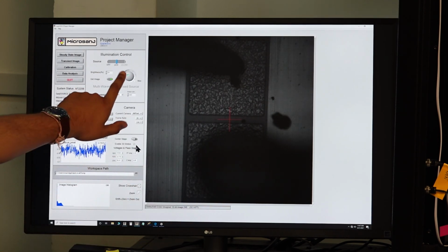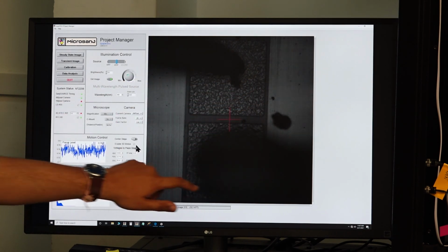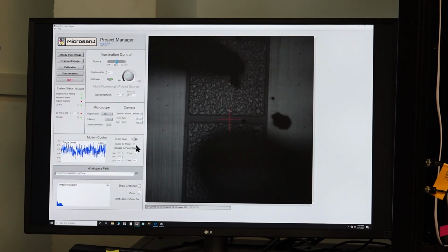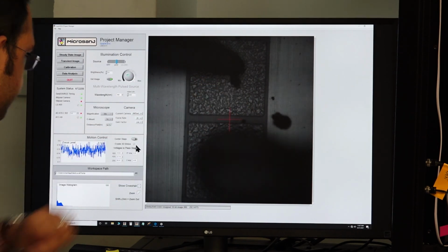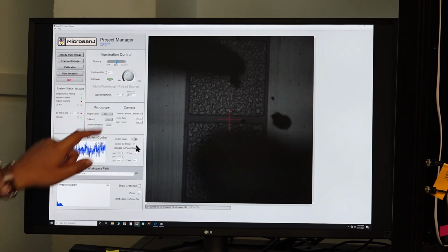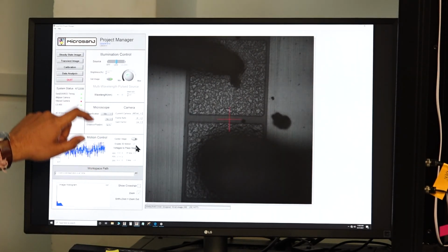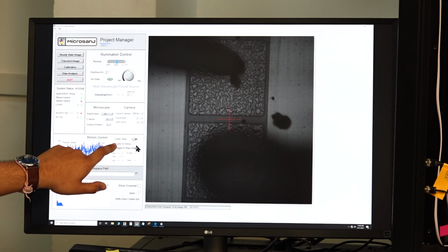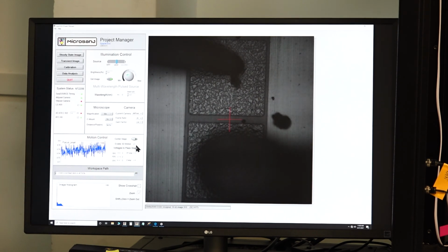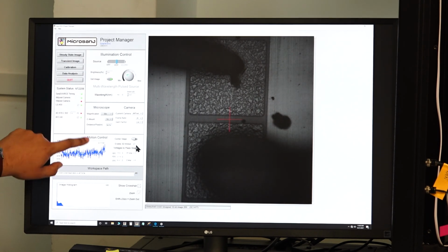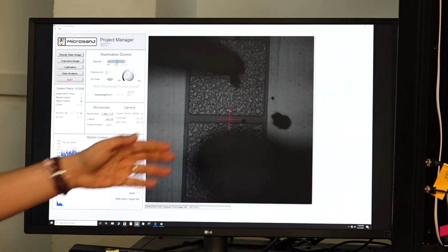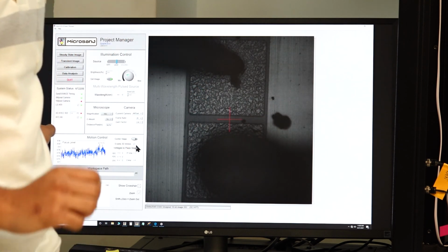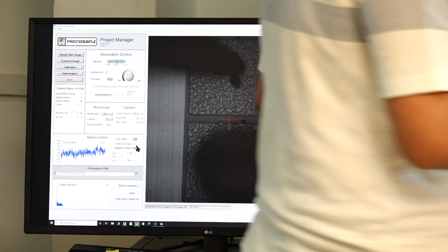We'll check that the brightness is sufficient so that this CCD image is proper, meaning the device is focused properly in the active region. In this case, this would be my active region. We must also ensure that the proper frame rates and gain factors are set. We must ensure that the center stage option is enabled and 3D motion is enabled. One more thing before I go to the next module: while focusing, one of the important parameters is this focus level. I'll show you quickly how this focus level changes when the focus is lost. This is one of the key things that will help you.